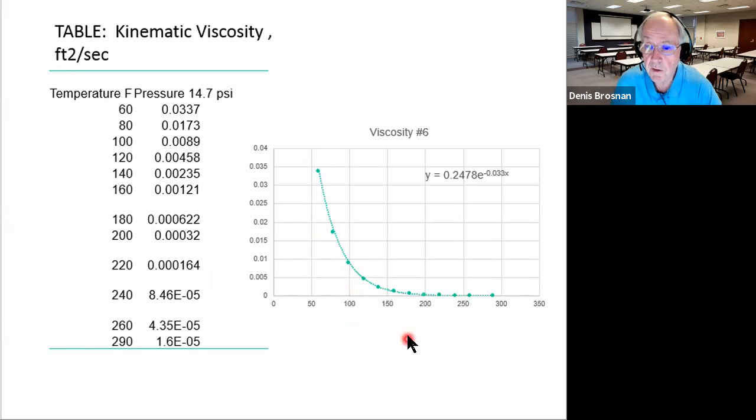And it fits pretty well. And then you, of course, can plot an equation here if you wish for viscosity. So somewhere up here, you're going to find a pumping range, and you're going to see down here what temperature you need. And then you'll see a vaporization range, and you'll see what temperature you need in order to combust that oil.